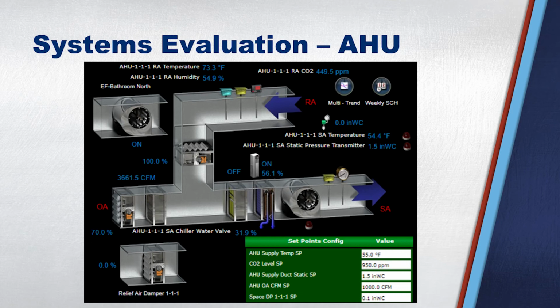And so that's one of those, hey, it's great that you have more outside air, but you really do want your system to work properly. So let's identify it as something to fix. One of the other ones that I love is every unit we looked at, right, Marcus? Every unit we looked at was 1.5 inches of duct static. For those of us that know, that's basically the number means it didn't talk to TAB and didn't get a real value because it works. So little things that you can help your owner.